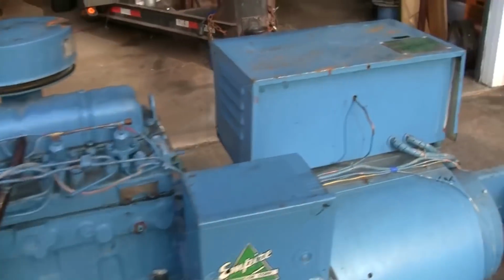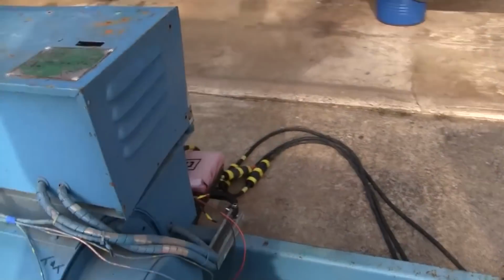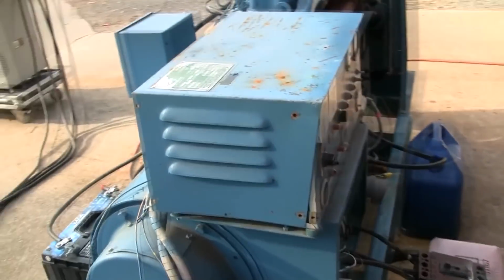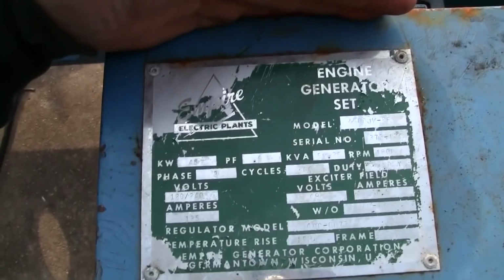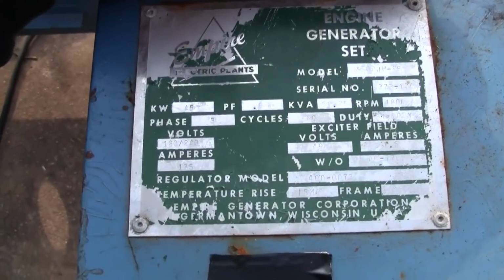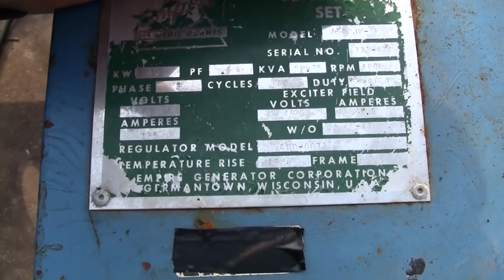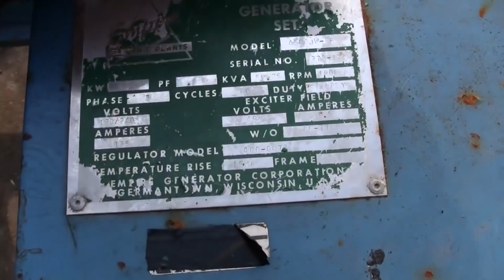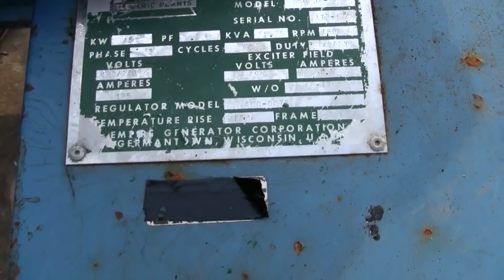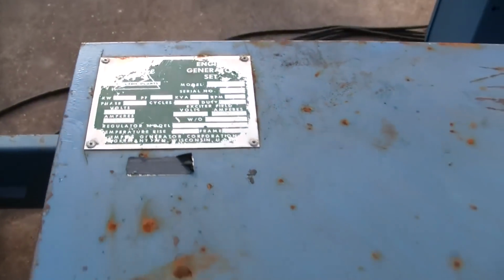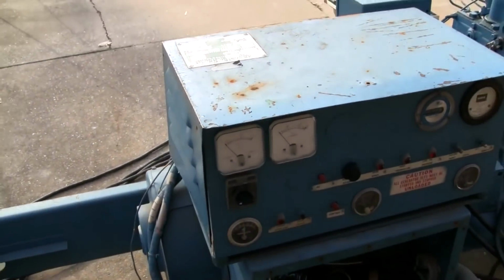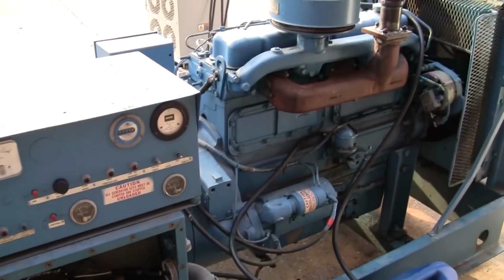Let's take a look at the nameplate for the generator. Empire Electric Plants, 45 kW, 3-phase. Right now it's connected for 120/240, which is a Delta connection. 1800 RPM. I can't say I've ever seen an Empire branded gen set before.